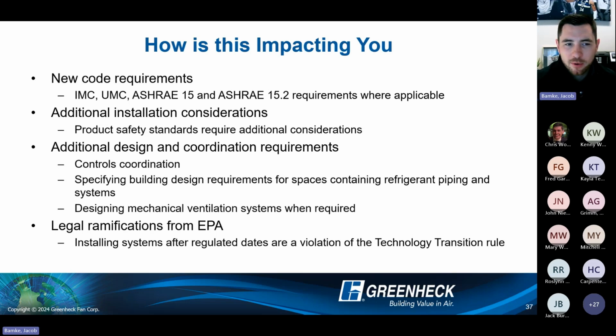Additional design and coordination requirements, whether it's controls coordination, which we'll talk about. You might have to specify some certain design requirements for spaces that actually have refrigerant piping and systems within them. And then you might actually have to design mechanical ventilation systems where required as well. And then lastly, the most significant one is obviously there's legal ramifications from the EPA if you install systems after regulated dates. So that's a violation of the technology transition rule. Manufacturers are adhering to it, and then obviously the field would have to from that sell-through or installation date standpoint as well.